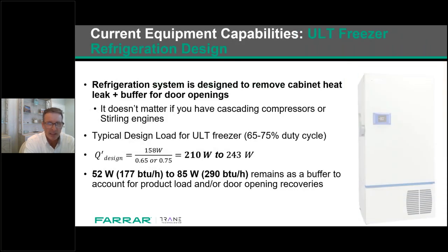So when we look again at the ULT freezer, cold wall minus 80 freezers are designed to maintain cabinet temperature, assuming the heat load comes from the leaks through the insulation, the door, and the door gasket, just like we went over a few seconds ago, and the recoveries from door opening. In order to design for the added cooling capacity, typically a buffer of 25 to 35% is added to the cooling capacity of the refrigeration system. So in this case, taking the 158 watts listed on the previous slide and adding 25 to 35% increases the yield to 210 to 240 watts of cooling capacity available.